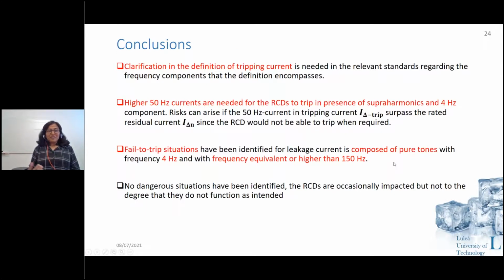Yeah, with this, I would come to some of the concluding remarks. A basic conclusion we came up with is that a clarification is needed in the definition of the tripping current, or what should be the frequency component, what should be the composition of the tripping current. Some standards already have a composite leakage current with which the RCD should be tested, but it is only till 1000 hertz and not above that. And there's no mention of quasi-DC currents in the leakage currents. So maybe that also can be included. A clarification is needed there, and also whether the RMS value should be considered or only the 50 hertz component should be considered when judging whether the RCD failed to trip or whether it was blinded. So that kind of conclusion.